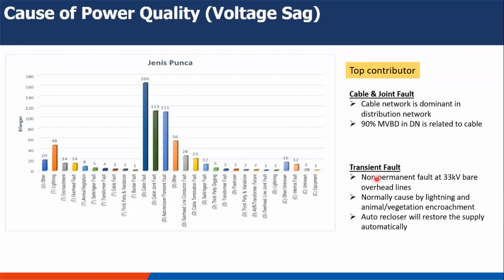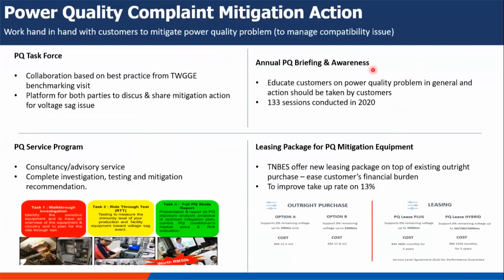The second contributor is transient fault. Some permanent lines have bare overhead lines with auto recloser, normally caused by lightning or animal encroachment. Then the auto recloser will close back when it detects a fault. So we can say that 90% is due to MV cable breakdown, because of the quantity of cables in the distribution network. So what has TNB done to mitigate power quality problems?